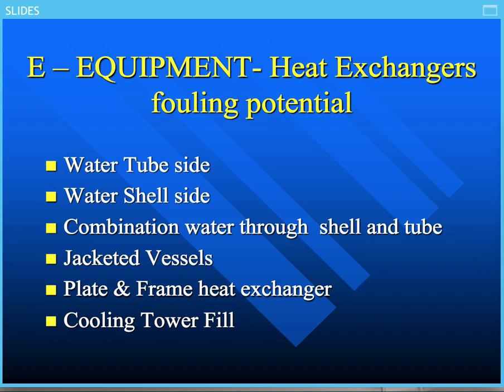So, and if you could have the combination of both, which is done in refineries and chemical plants, that makes it even more difficult for your treatment program. But it does indicate to you that you are going to be dealing with possibilities of fouling conditions. Jacketed vessels are prone to fouling as well. And don't forget the plate and frame heat exchangers if that's being utilized in your system. Last but not least, of course, is the cooling tower fill itself.